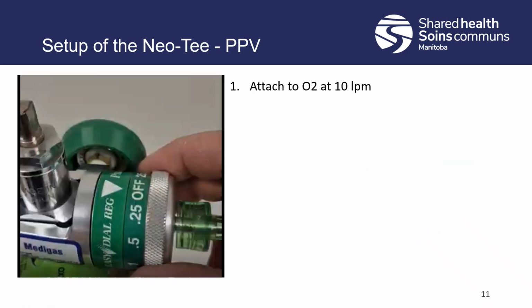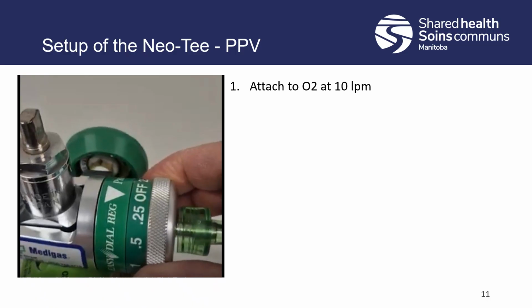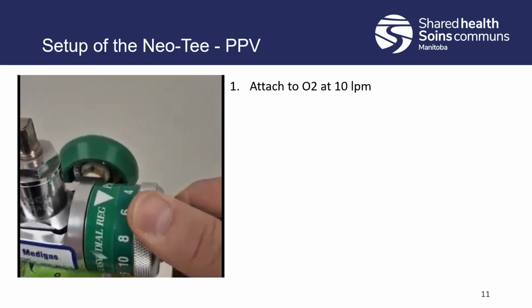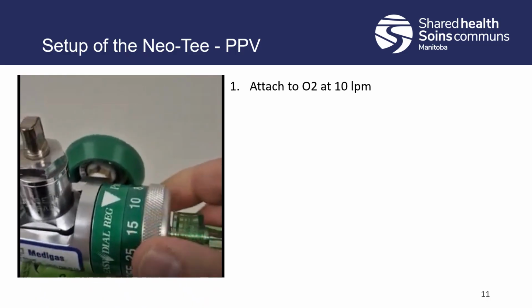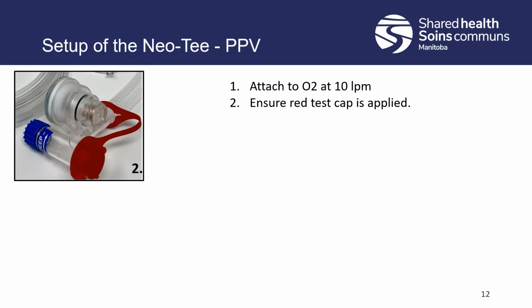So the first thing we're going to do when we set this thing up is attach our O2 and set it to 10 lpm. We have to have the O2 set and going so we can dial our pressures in appropriately. We're going to make sure the red test cap is applied to the end of the device. Where the red cap's sitting, as you can see in the picture there, that's what's going to actually attach to the baby. So we're going to block that off because that'll tell us our pressure gradients, because we obviously want to do this before we put it on our baby, because the last thing we want to do is start ventilating our neonate and find out that our pressures are way too high.